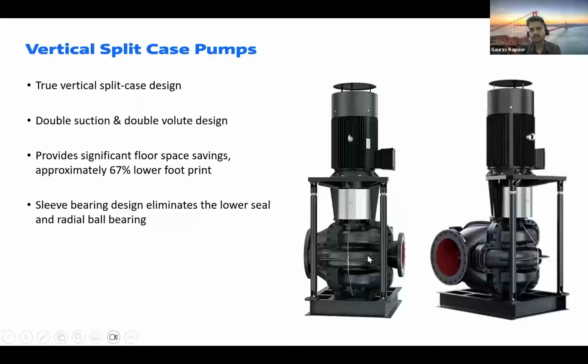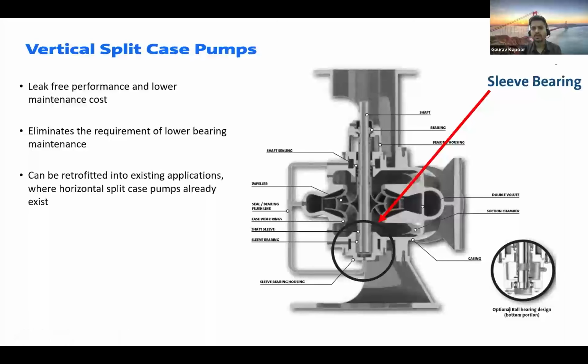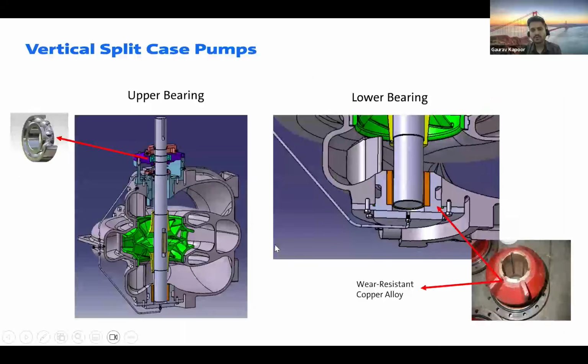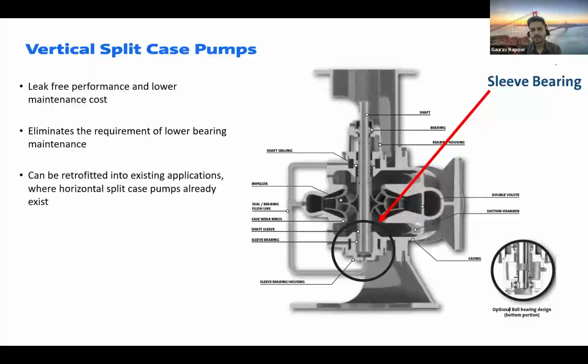Now they also come in a vertical design in case you have space constraints. So it's the same vertical split case. Your suction and discharge come in line. You open these bolts and you can directly access all the internal components of your pump. Now one thing which is always important to remember is that in vertical and horizontal split case, design wise they both look the same, but there is one major important factor: this is the drive end, where the motor will be connected on the top, and this is the non-drive end.